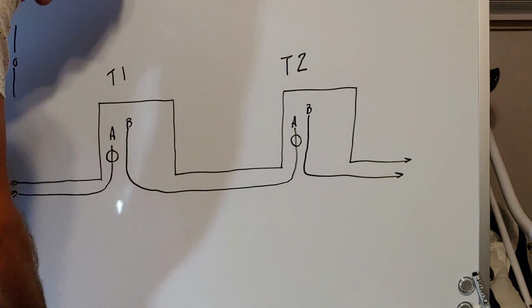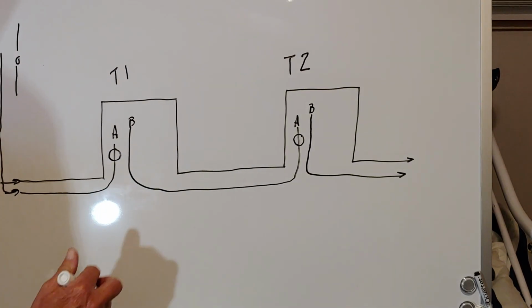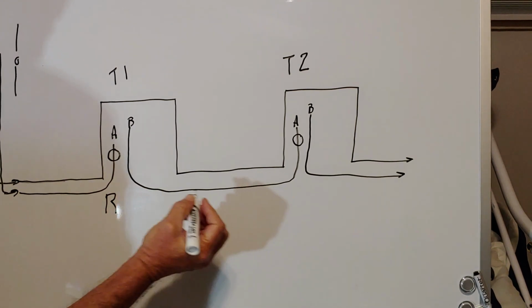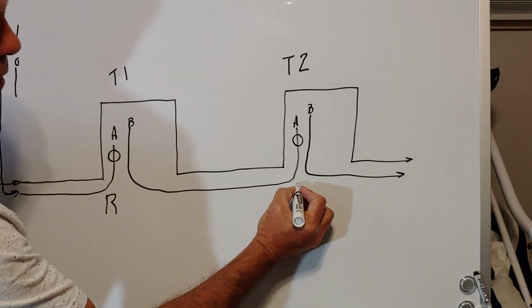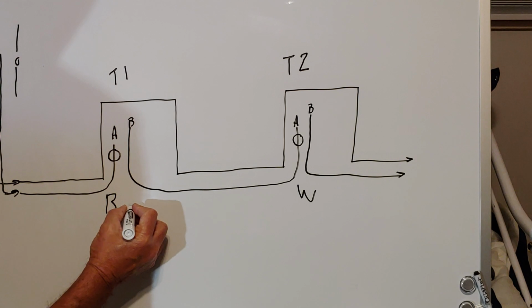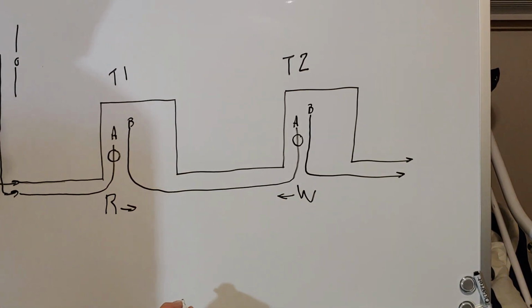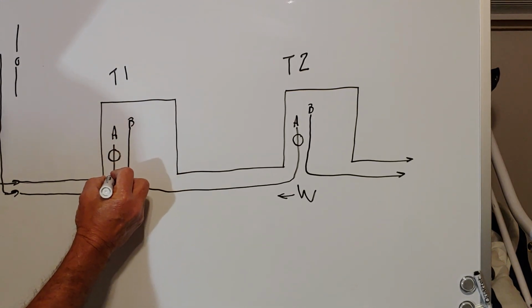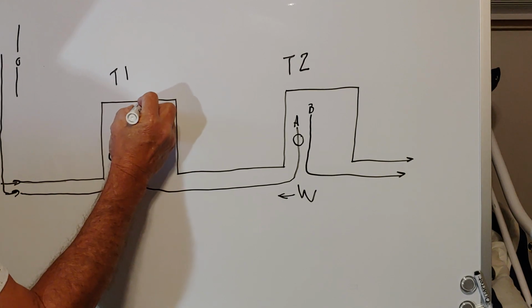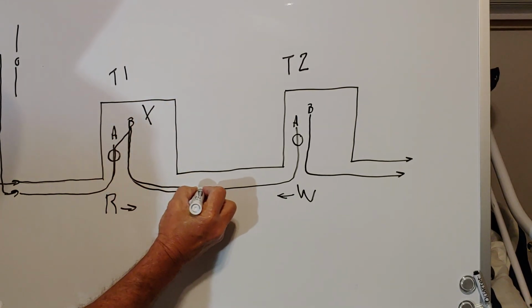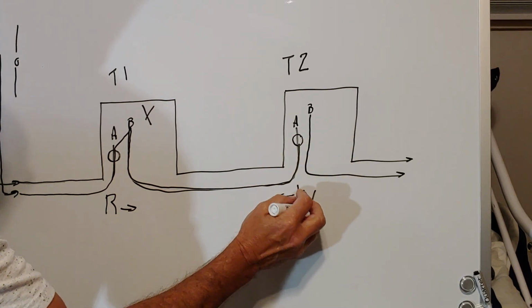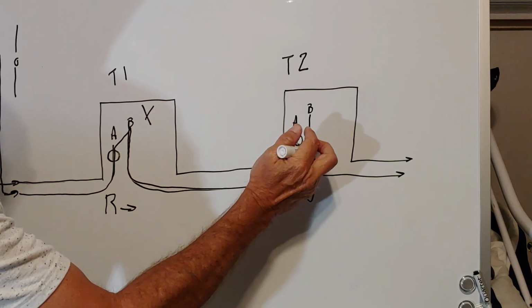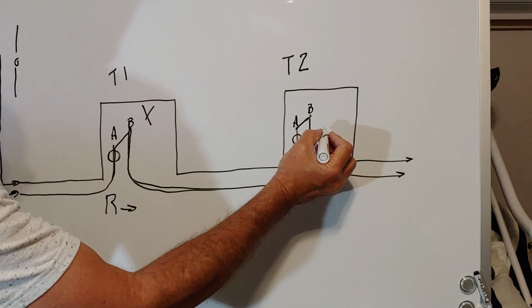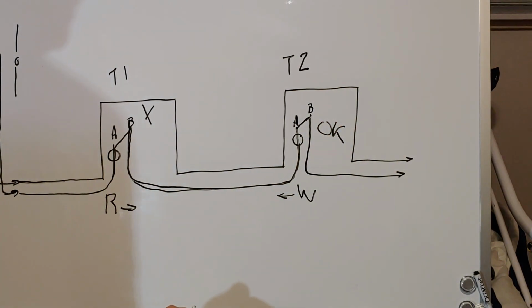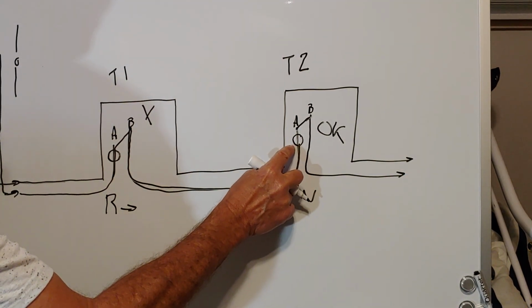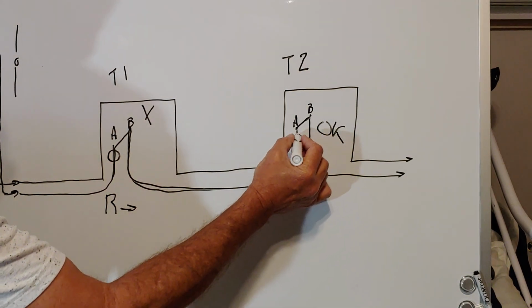So let me get down here and I'll show you. So what we'll have here is a red indicator. Since we're just using two transformers, we'll go white. So somewhere in this span, like I had described in the video before, we have a fault. Now, that's going to include the transformer itself, out, and in. Now remember, if this one is white and we have the indicator on the cable right here, everything beyond is okay. So that includes this transformer. That transformer is okay. Everything beyond is okay because we have our indicator on the inbound cable. That's where it's going to stop monitoring right there.